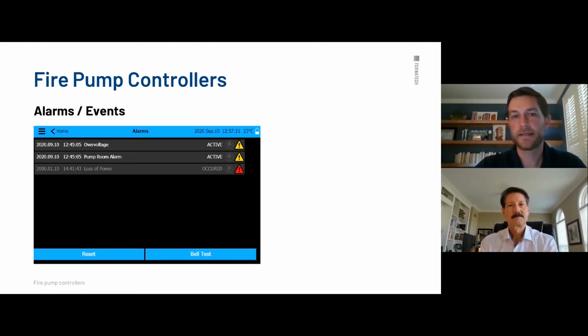We want that to be acknowledged, so it will show up in this alarm page until somebody comes in here and says reset. So you can see that down here on the bottom left. Once you reset, it'll clear all the occurred alarms. Active alarms, however, will not be cleared. As long as they're active, they're going to stay there no matter how many times you push the reset button, because there's something that needs to be taken care of.